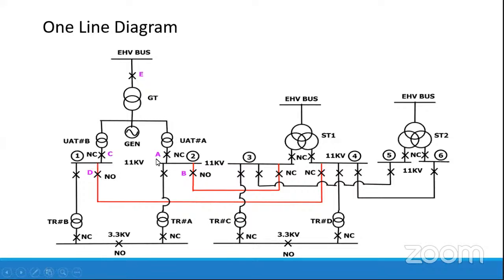Here the NC indicates normally closed, and NO indicates normally open. As I said earlier, we need to understand the operating philosophies. In normal condition, if we have power from the EHV line and from the generator, then the fault current of the system will be different. And if only the grid is feeding the power, then the fault current will be different. So for this relay coordination, we need to understand the different operating philosophies of our system.